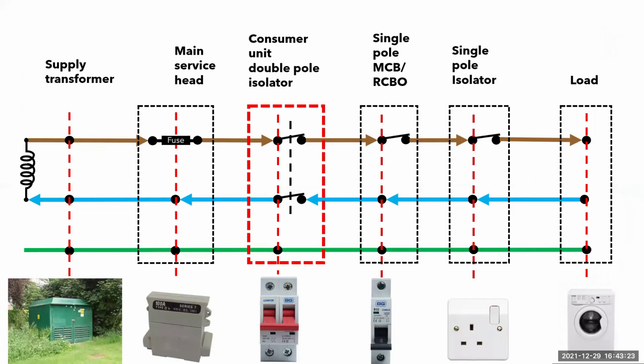And the process repeats itself as we work our way through the circuit, with the exception of the consumer unit's main switch. Unless there is an external isolator between the electricity meter and the consumer unit main switch, you have no way of isolating the supply from the main service head, at which point you should contact the DNO and ask them to remove the fuse for you. For instance, this will enable you to change the consumer unit safely, and it would probably be worth putting an additional isolator between the meter and the consumer unit for future consumer unit changes before the DNO replaces the fuse.